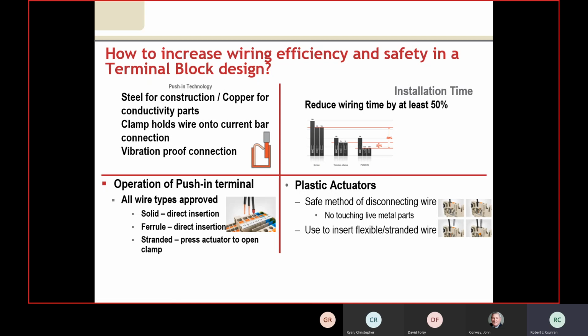More and more customers are starting to go to spring clamps, and we're noticing more customers are starting to go to the ferrule. Rexel has them, and Panduit has the ferrules too. They also have a device for those of us enamored with mechanical devices that will strip and insert the ferrule all at one time. You just put the wires in, you don't have to strip them, and you watch it do that. Being a mechanical guy, I just stand there trying to figure out how it's doing it. It's a very fast way to wire those up.